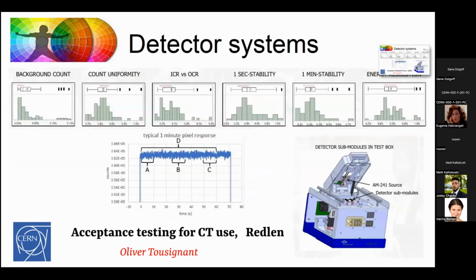Oliver from Redlen in Canada, on Vancouver Island, they've been producing semiconductors for photon counting. So by high-Z semiconductor, we use something like cadmium zinc telluride. Because it's made of cadmium, zinc, and telluride, they're heavy atoms, they stop the X-rays quite well, a little bit like lead stops X-rays quite well. But as a crystal, it's a semiconductor like silicon. So you can stop the X-rays and you can conduct out the charge cloud and analyze the charge. And they've been building test units where they can look at the quality of the crystals that they're producing. And that sort of technology is what's required to take into medicine. It's not an experiment. You produce thousands and thousands of crystals, the same quality, and you measure the quality, and what goes into the hospitals is well understood.